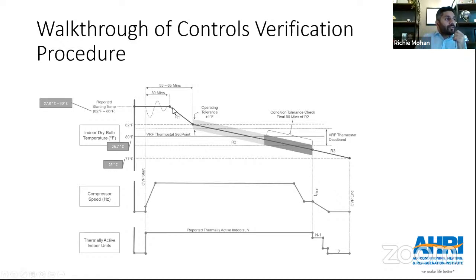Subsequently, we start ramping down the test chamber temperature. This is the R1 out here. The ramp down will happen until we get very close to the set point thermostat deadband. So if you put your set point for this VRF system at 26.7 degrees Celsius, then most likely your thermostat deadband would be either 1, 2, or even 3 degrees Celsius. Whatever that deadband is, plus or minus, you want your ramp down to come right at the edge of that thermostat deadband.